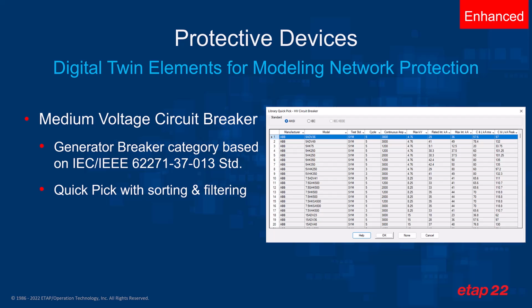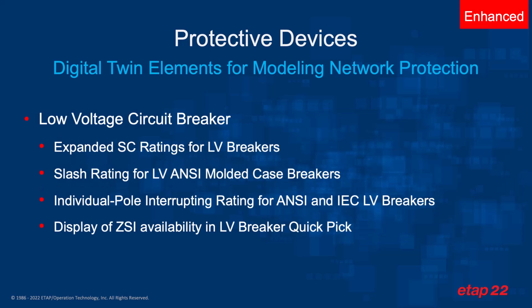You can essentially choose from ANSI, traditional IEC, as well as IEC/IEEE within the circuit breaker library and pick the manufacturer and model of your choice and use it within the simulation. The quick pick for the circuit breakers has also been improved, including a quick pick with sorting and filtering capabilities, allowing you to quickly find the manufacturer, model, or a circuit breaker based on its size or rating very quickly and efficiently. There are similar standard improvements also for low voltage circuit breaker.